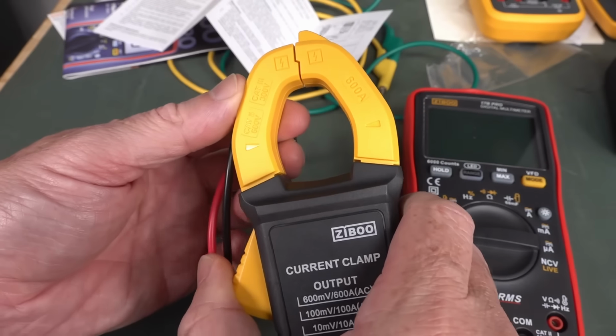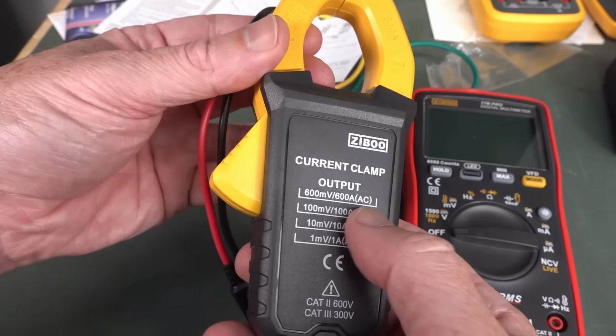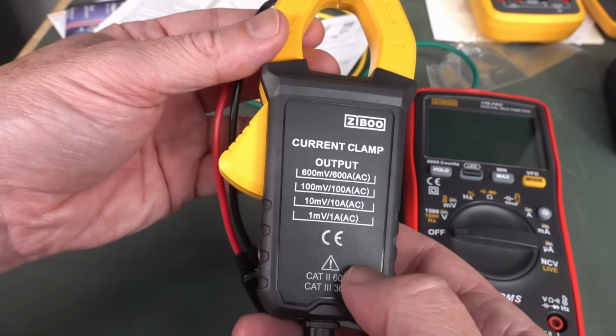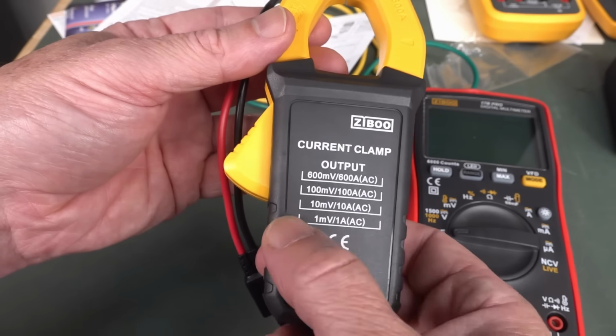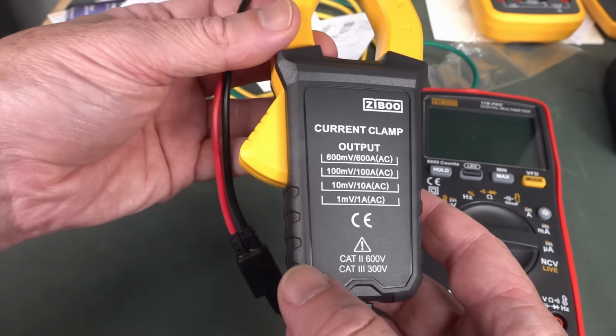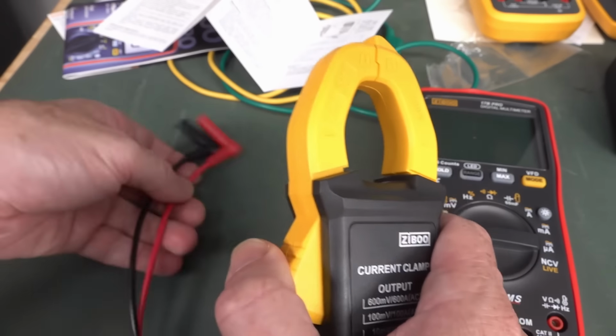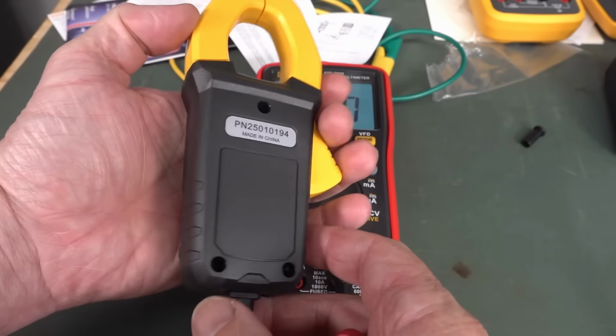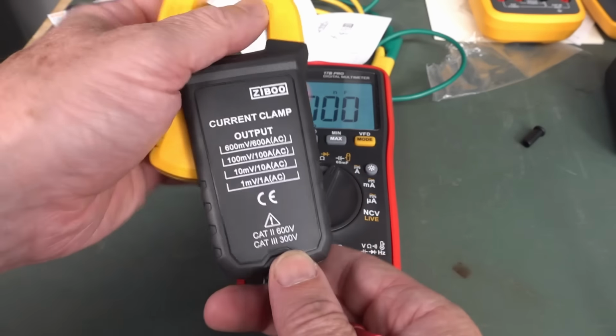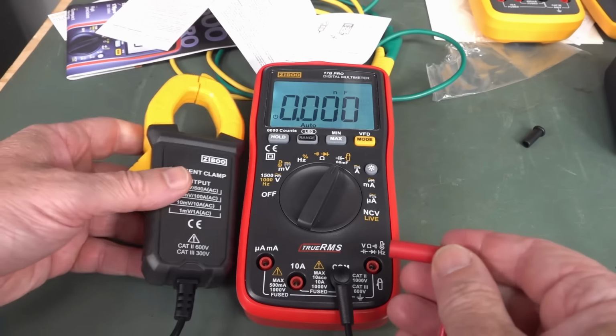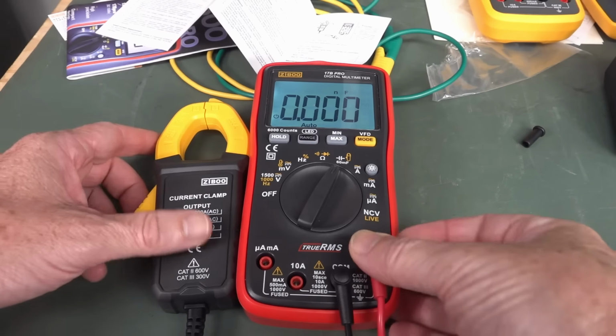Anyway, it's got your usual clampy jaws, pretty good. It's rated for 600 amps maximum, will give you 600 millivolts, 100 amps, 100 millivolts, 10 amps, and 1 amp at 1 millivolt. So it's not for low current, it's for big current jobbies. And there's no batteries in this, it's just a current transformer, so you can use this with any multimeter, it doesn't have to be this one.